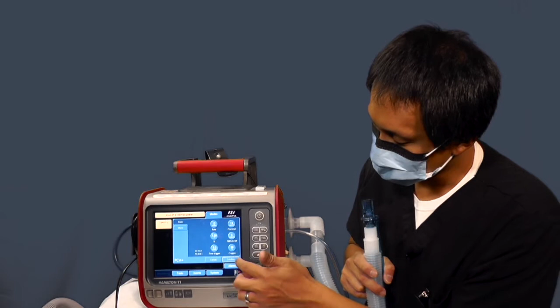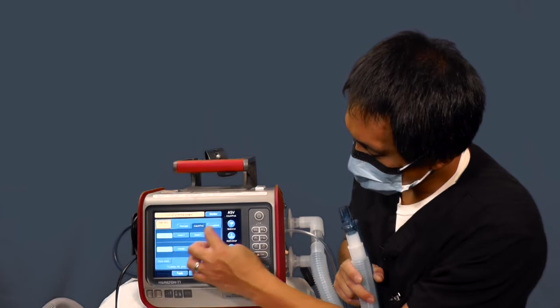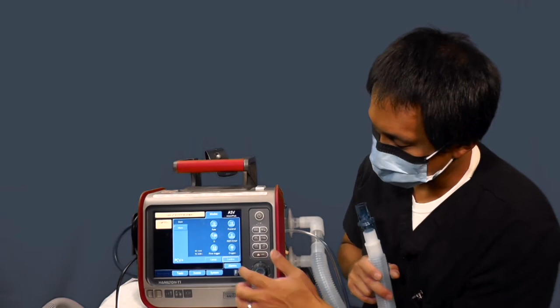so it does not ring off low oxygen since I'm not connected. Couple differences between this and the Impact is that your P control, which is your driving pressure, is a delta pressure and not a total pressure. So this is not compensated. So your total pressure on this ventilator for a setting of 15 and 5 of PEEP is actually 20. Something to note.